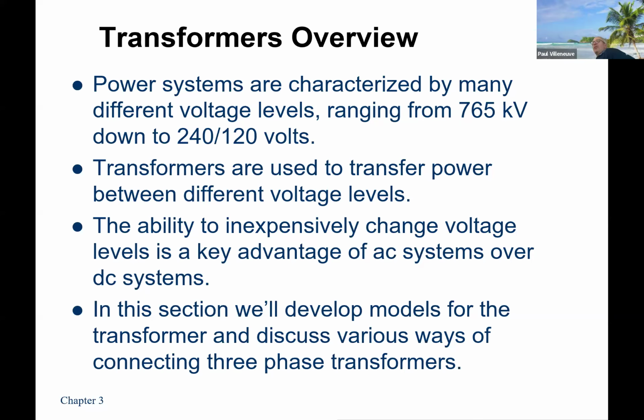And then the problem with transformers is it's a physical device. It's got a set of windings. It's got iron in the core. It also may have some oil, or it could be a dry type insulation, which would be an epoxy. It's a pretty complicated piece of equipment. Yes, sir. For isolation? Absolutely. Anybody know what we're talking about when we talk about isolation?